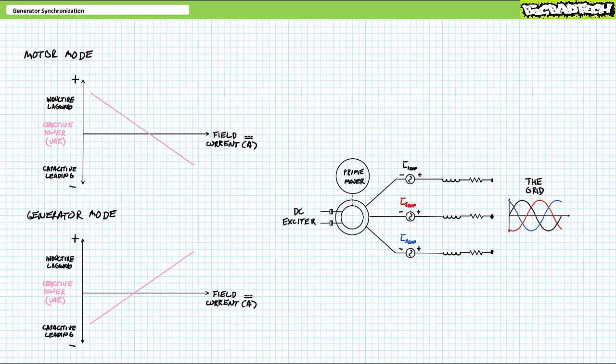Let's bring this lecture to a close. In conclusion, we examined generator synchronization. We learned generators can be synchronized with the grid only when their phase sequence, phase shift, frequency, and voltage magnitude match that of the grid. Additionally, we discussed how synchronization lamps and synchroscopes can be used to manage synchronization events, and observed how improperly managed synchronization can generate undesirable electrical and mechanical transients. Finally, we learned how generators, once synchronized with the grid, export real and reactive power to the grid. Once synchronized, rotational speed remains fixed, however increases in torque result in generation of more real electrical power. Similarly, once synchronized, voltage remains fixed, however adjusting field current changes the reactive nature of exported electrical power.